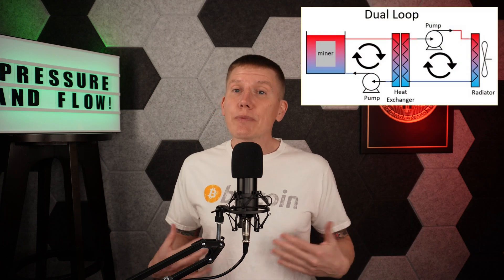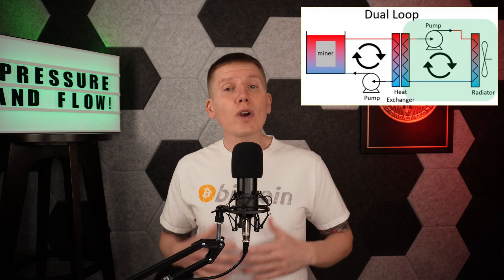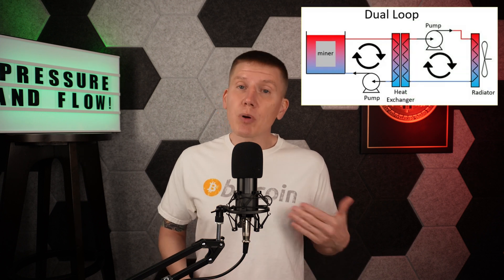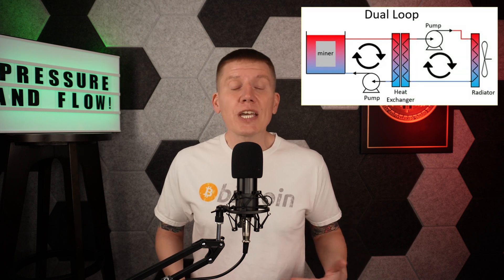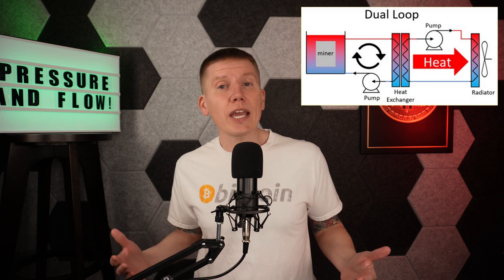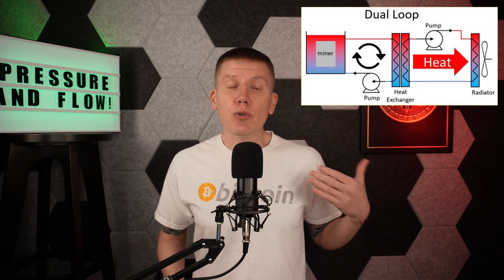On with the episode. In this episode, I'm going to cover the design of the radiator cooling loop for a dual-loop immersion mining system. The purpose of this loop is to transfer the heat from the heat exchanger to the radiator outside the house, where miner heat is going to be released into the environment. This loop can also be used to transfer heat to your furnace, your hot water heater, and wherever else in your house you want to use your miner heat.